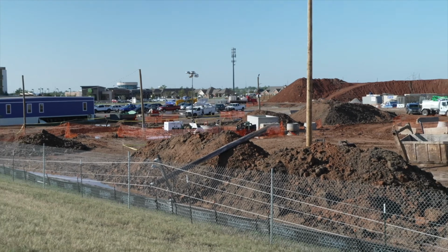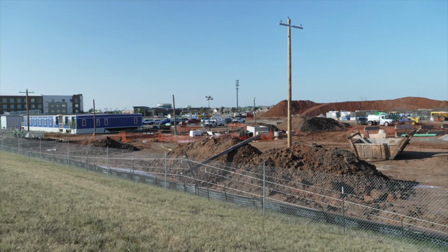Now, that area that's damaged, we can sectionalize it. We can open a breaker on the other end. So a very good example is we had a breaker on the grid open up, drop off an entire part of town. Part of that was involved in our new ACES project, and we just opened the breaker where we connect to the grid and then closed in a breaker to another town, and we instantly refed 1,000 people. So those 1,000 people were able to instantly come back online.